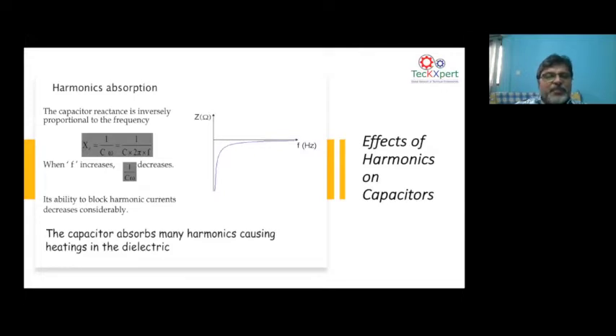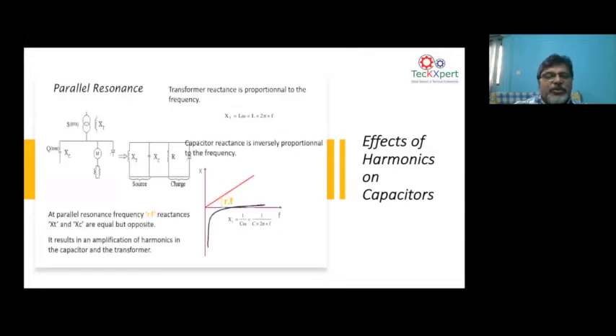Go to the next. Now, the biggest problem when you put a capacitor in the network, you can see in the single line diagram drawn on the left side. You have a source transformer, you have a capacitor bank, and you have a harmonic source. Now you have another motor, which is an inductive motor. There's no harmonic, no power electronics or VFD there. But then you have a power electronic device sitting as the third branch of the single line diagram. And now you can see that that is a harmonic producing load.